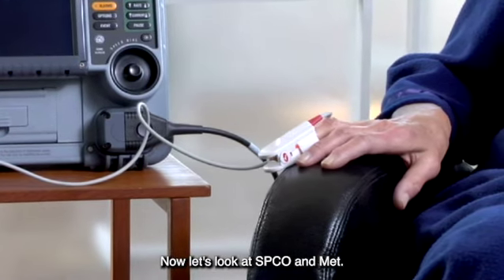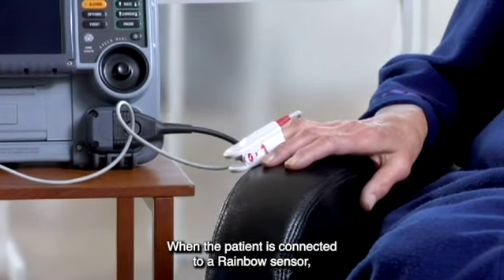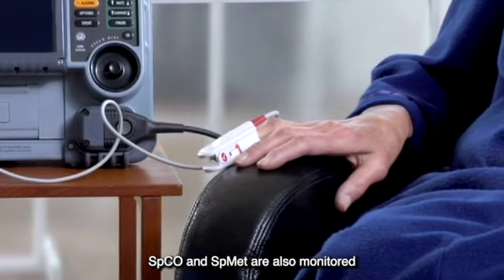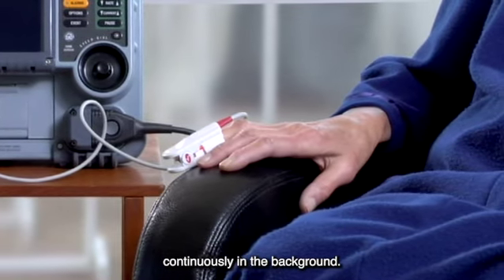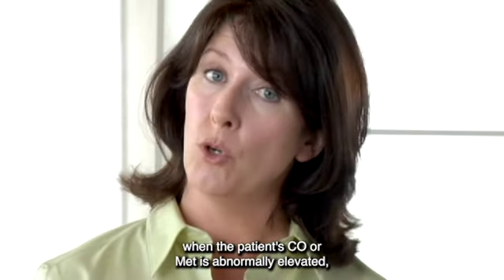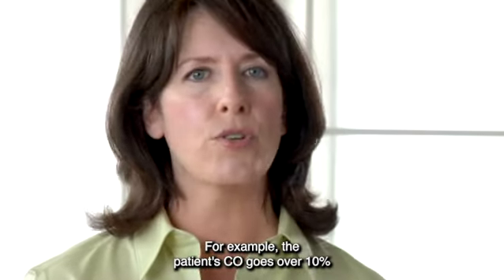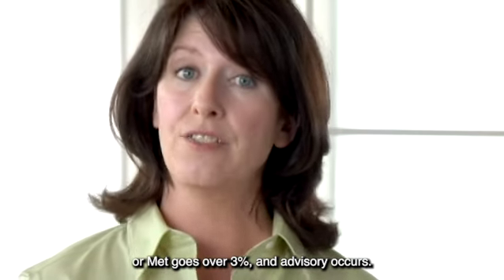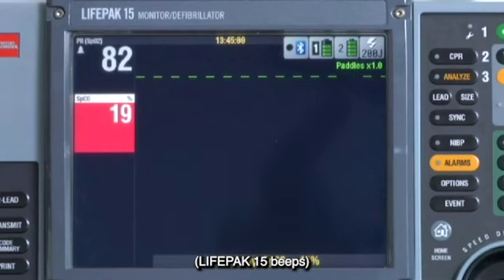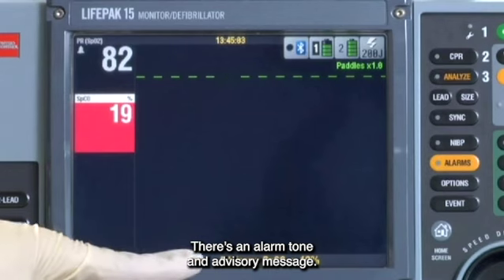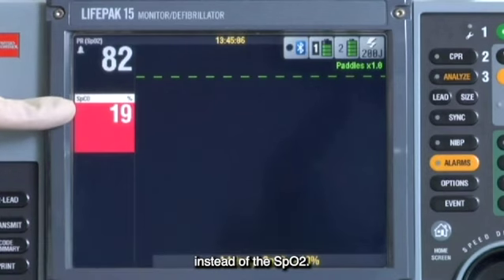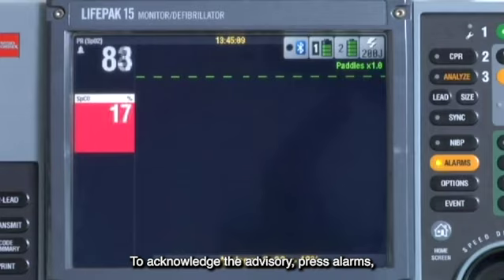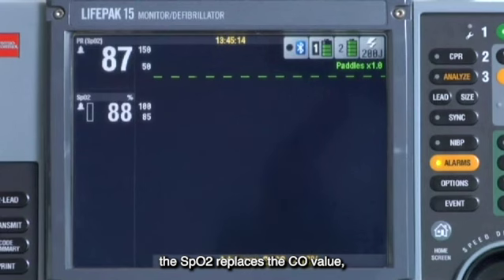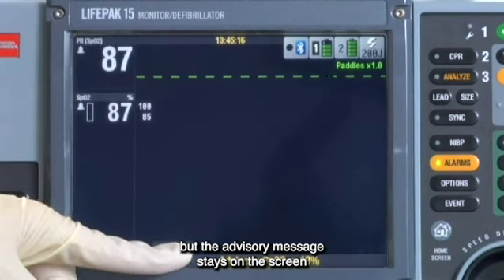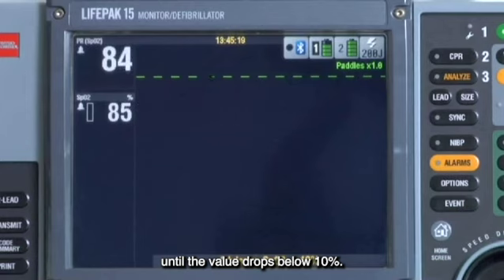Now let's look at SpCO and SpMET. When the patient is connected to a rainbow sensor and we have a good SpO2 reading, SpCO and SpMET are also monitored continuously in the background. When the patient's CO or MET is abnormally elevated, for example, the patient's CO goes over 10% or MET goes over 3%, an advisory occurs. There's an alarm tone, an advisory message, and the elevated value starts flashing here instead of the SpO2. To acknowledge the advisory, press Alarms. The SpO2 replaces the CO value, but the advisory message stays on the screen until the value drops below 10%. The SpMET advisory works the same way.